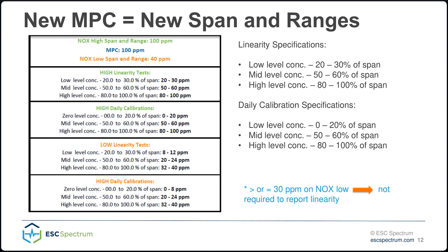There's more to it than just having a lower MER; it can save you in other ways as well. Keep in mind: if you are dual range and your NOx low span is less than or equal to 30 PPM, you are not required to report a linearity. I'm not certain ECMPS would even let you try to report a linearity if it was under 30 PPM. So when you do this evaluation, if your NOx low is going to be 30 PPM or lower for your span and range, you don't have to report that linearity anymore.